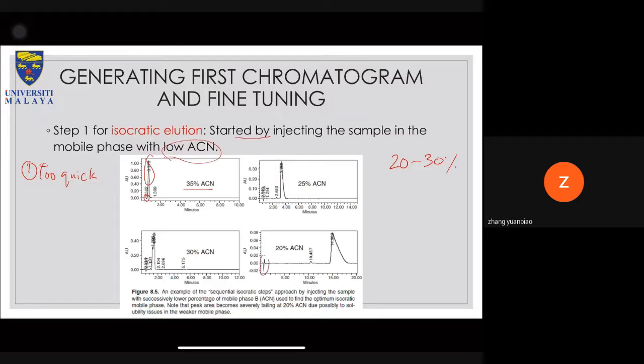Okay, if you see here, the initial bit of an HPLC run is normally where you see an injection peak. I like to call it an injection peak because when you inject your sample, depending on the gradient of the HPLC itself, you can prepare your sample in a different solvent than the solvent that you want to use to run your HPLC. So this is the solvent peak that you will see if that is what you did. Say, for example, you prepare your sample in methanol, but your HPLC run is in acetonitrile, you will see a peak like this emerging. Even if you prepare in methanol and your system runs in methanol, you will definitely see it. Either the peak is small or it's big. Okay, so you want the peak to be very visible.